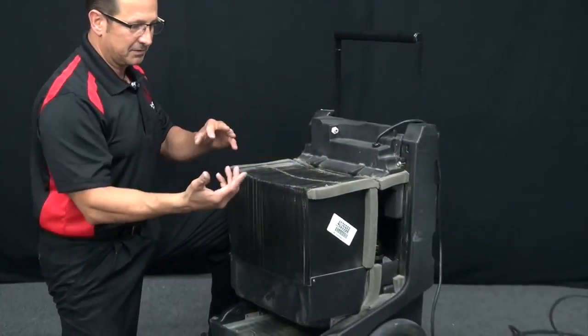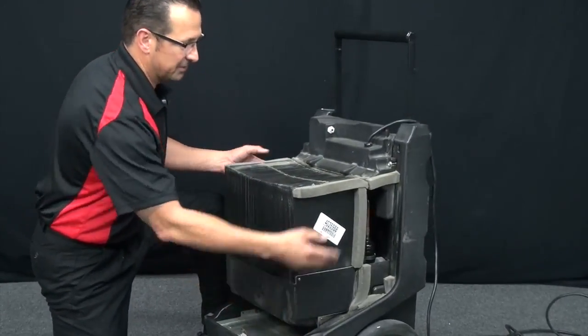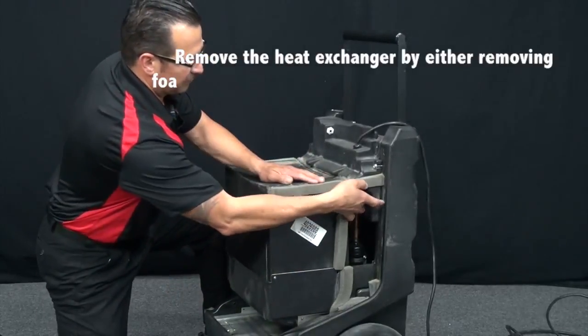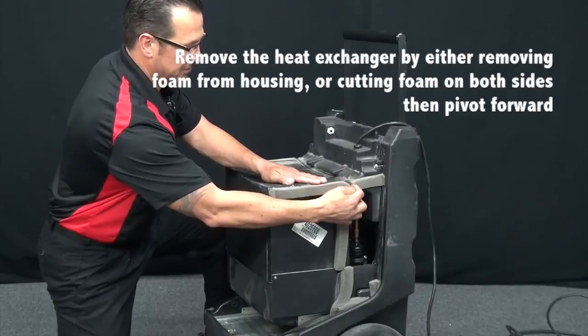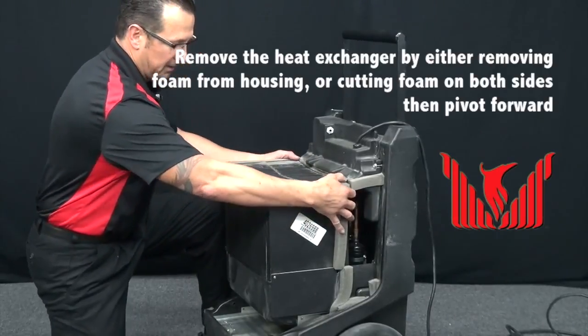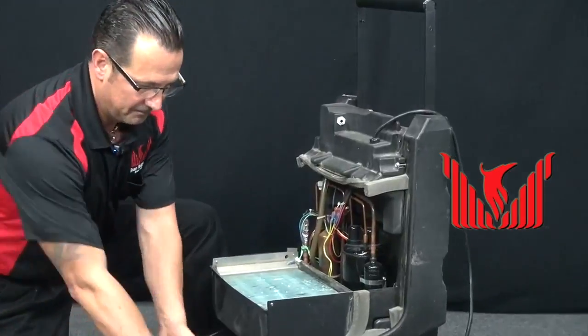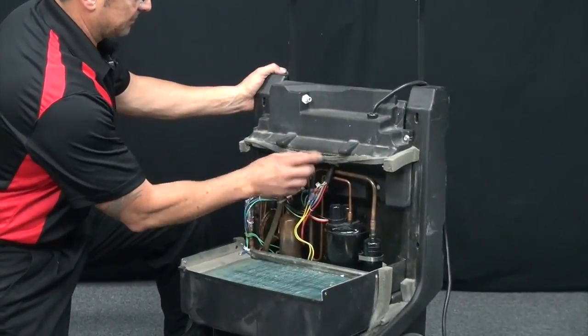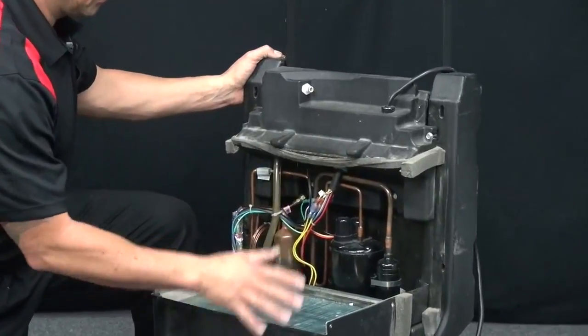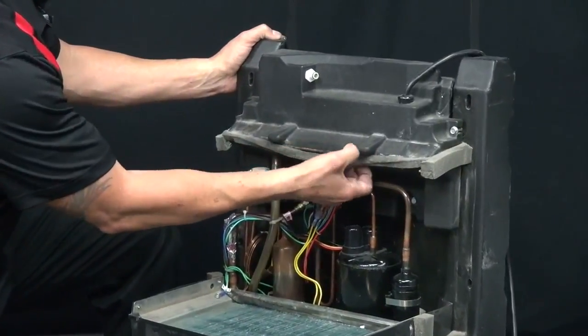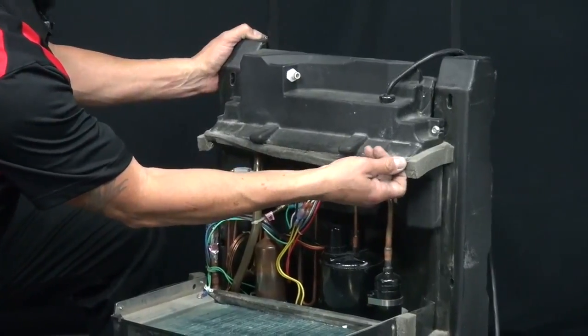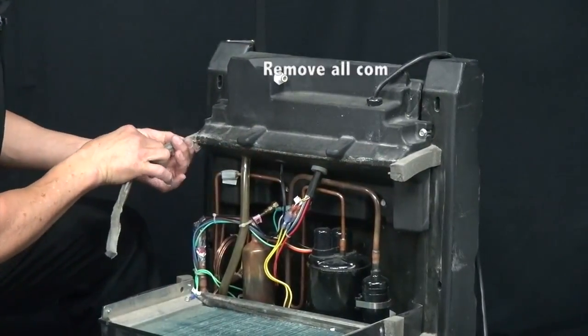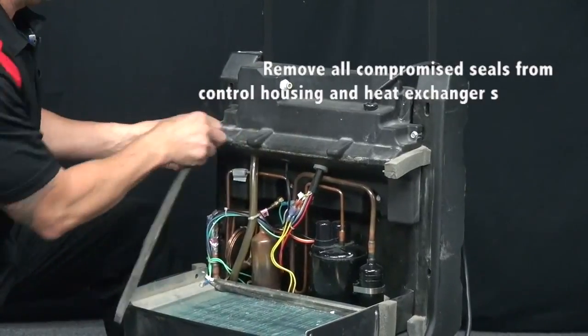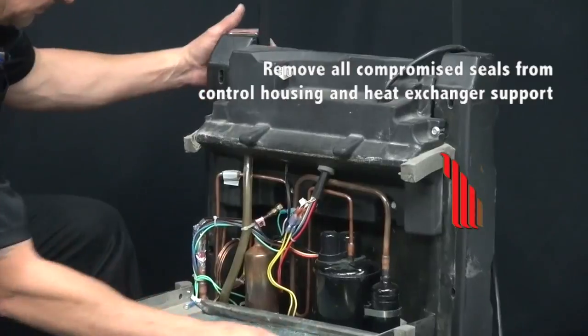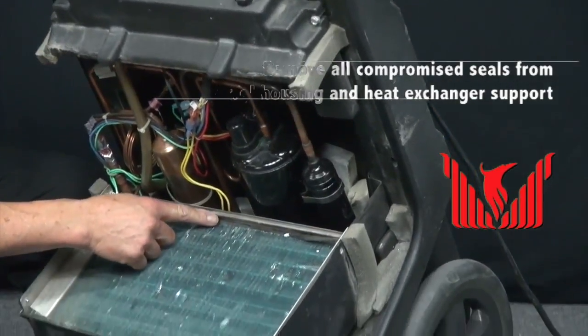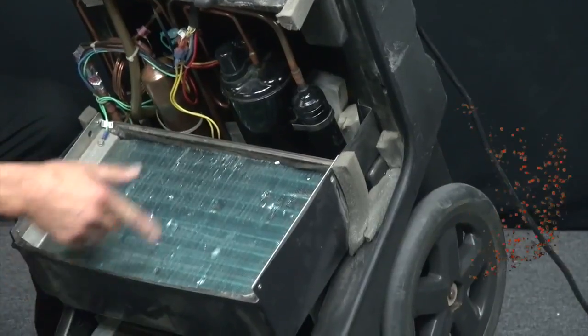First thing you do is, once you take the front cover off, we have to remove the heat exchanger. And to do that, you could either remove the foam tape from the unit itself, or you can actually use a razor knife and cut it here and here and simply pivot the heat exchanger out of the way. Next thing, as you can see here, the seal that seals the heat exchanger to the upper housing is compromised. So what we're going to do is remove this seal. And also, if you look here at the bottom, this seal and this seal are also compromised, so we're going to remove those too.